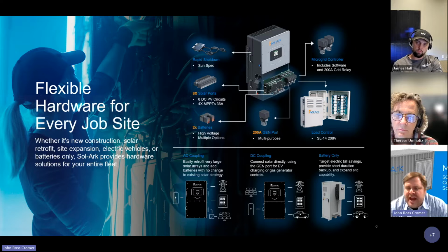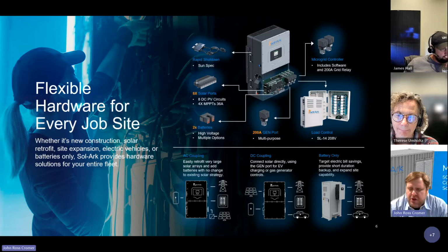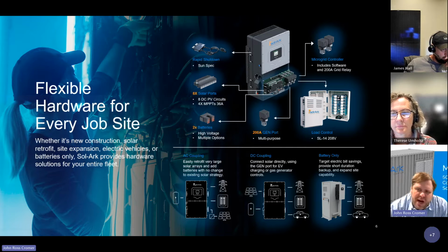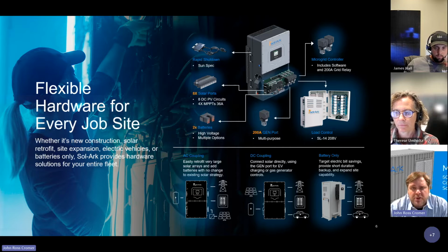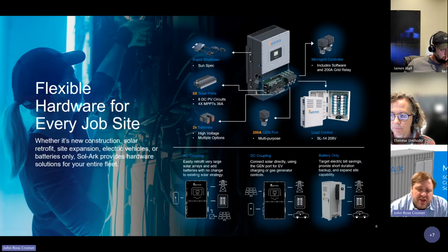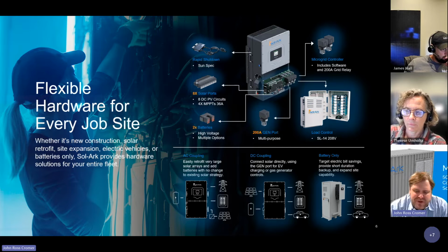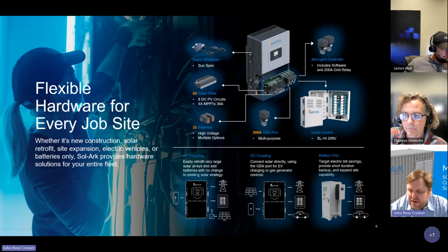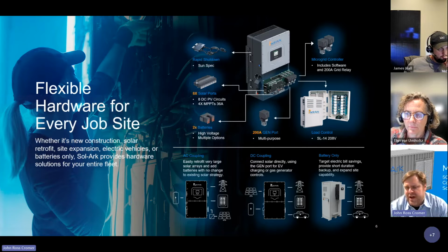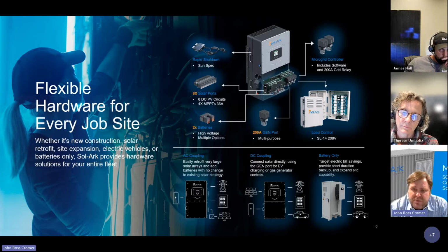It has the grid connection. It has a grid input and a load output, and it has that additional generator port. We have different inverters for 208 3-phase and 480 volt. The 208 3-phase version, our SL14, when it comes out early next year, will support 208 3-phase applications so that you can accomplish load control with 208 3-phase. That allows you to do that 1200 amp pass-through and then throttle most of the building down so that the building can operate in a backup mode of operation when the power goes out. That's more within the ampacity of what the inverter system can provide. So that's real interesting because whole building backup really hasn't been a thing yet. Likewise, a lot of 1200 amp panel boards have 200 amp load centers on them.